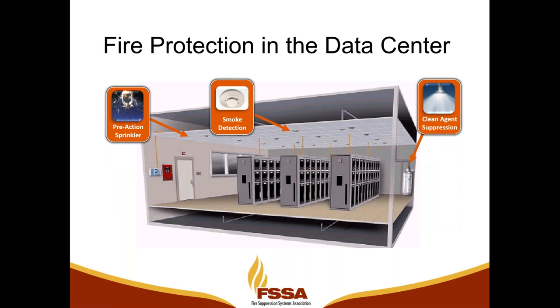And so as we talk about fire protection here in the data center, there are three main systems that get affected by aisle containment systems as they're applied to the data center. Of course, smoke detection, often used in data centers so we can have early warning of a fire, can be affected by aisle containment. The sprinkler system, whether it's pre-action or wet, will be affected by the partitions installed for the containment system, and the gaseous clean agent system, if one's there, can also be affected. And so as we dive in further here, we're going to talk about some of the challenges to those systems when aisle containment systems are installed.